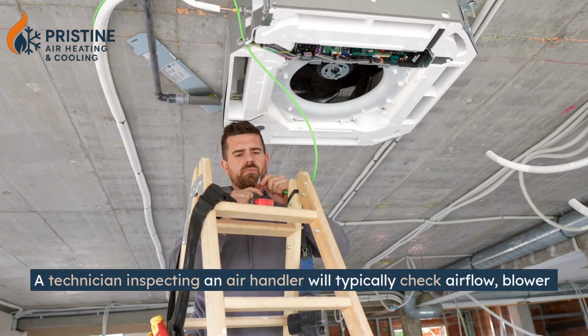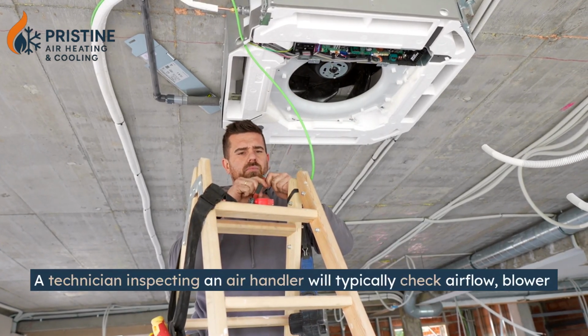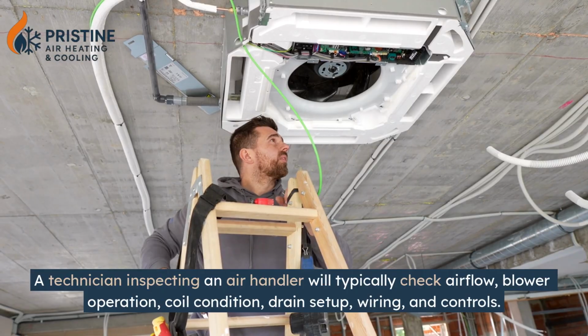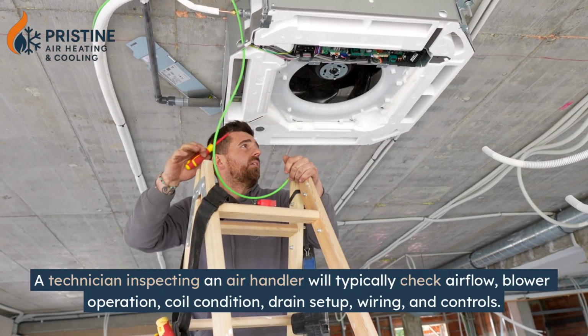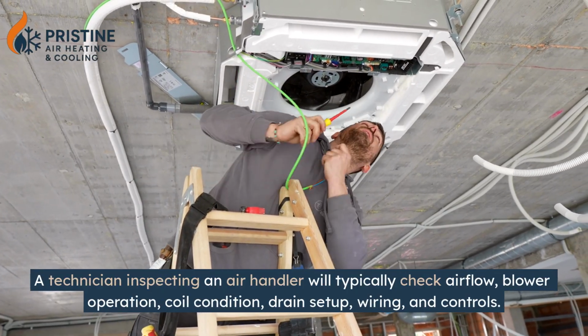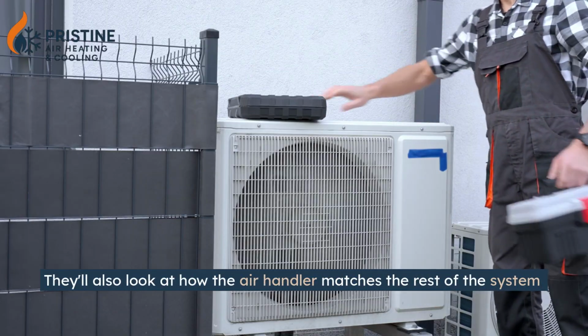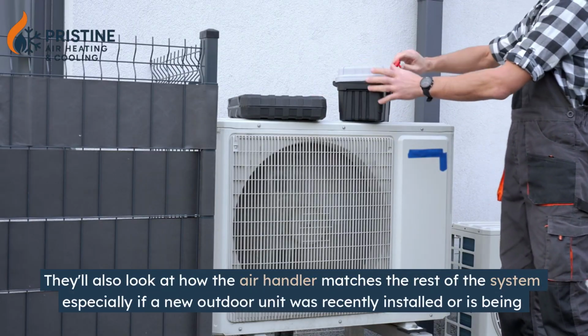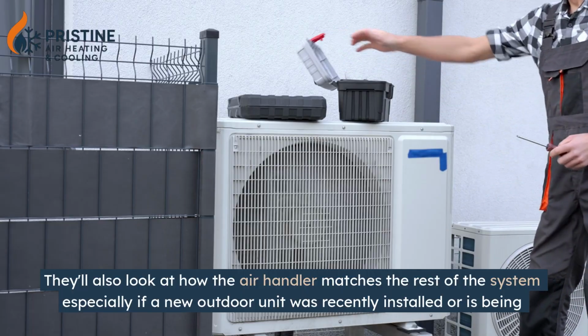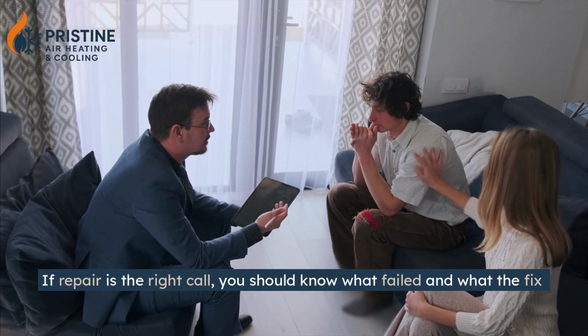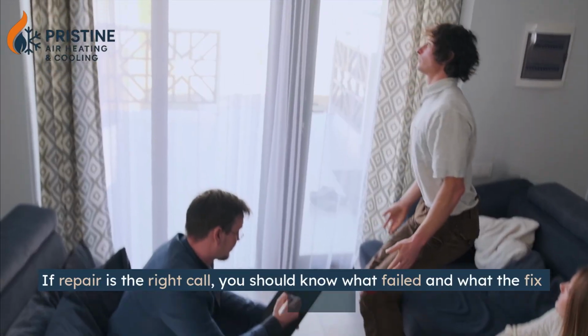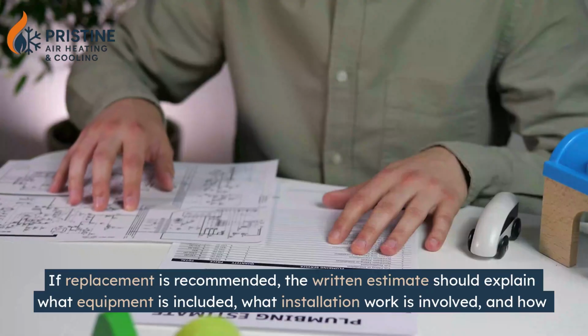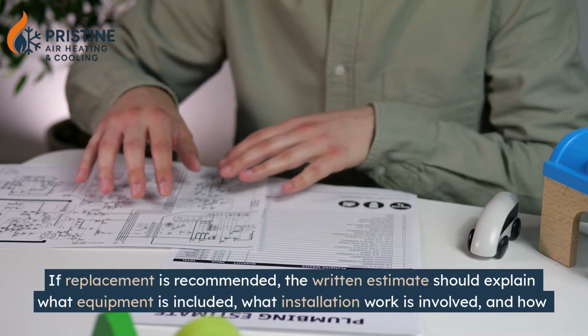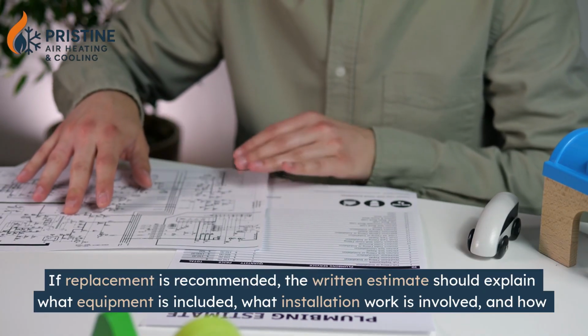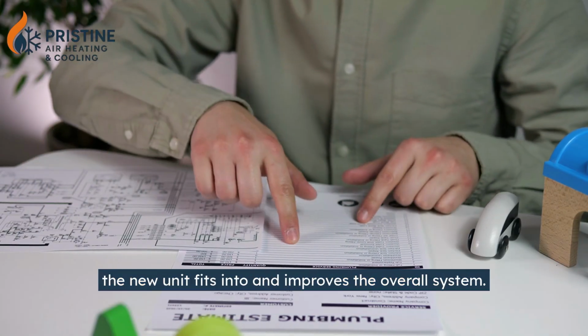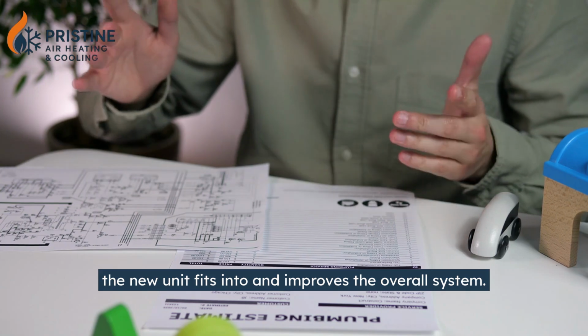A technician inspecting an air handler will typically check airflow, blower operation, coil condition, drain setup, wiring, and controls. They'll also look at how the air handler matches the rest of the system, especially if a new outdoor unit was recently installed or is being considered. If repair is the right call, you should know what failed and what the fix involves. If replacement is recommended, the written estimate should explain what equipment is included, what installation work is involved, and how the new unit fits into and improves the overall system.